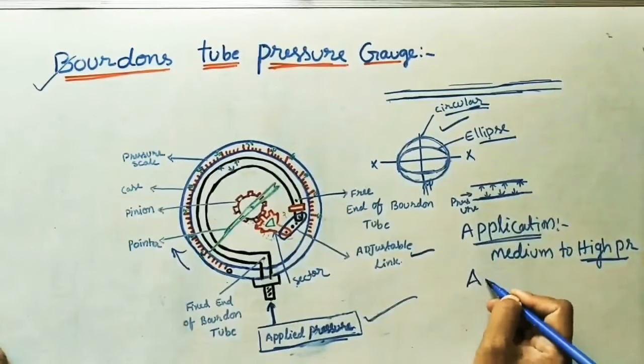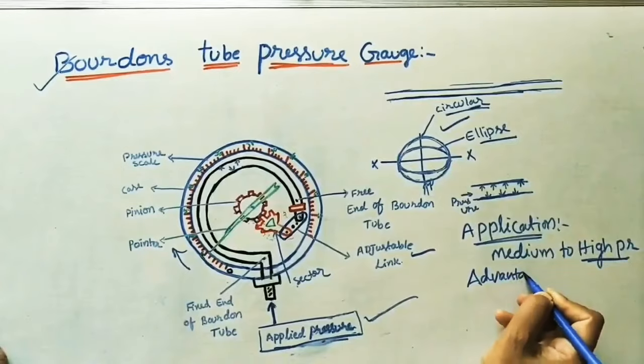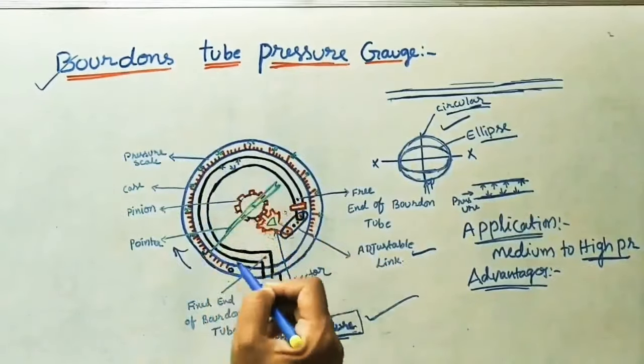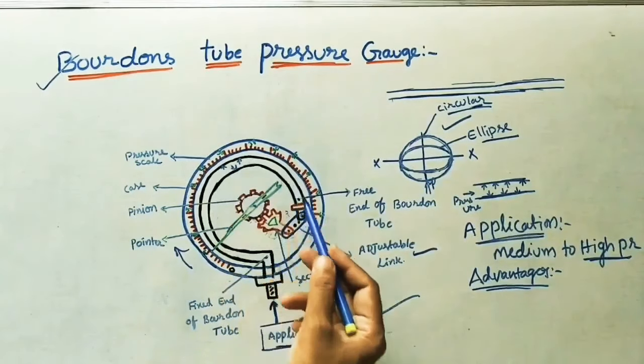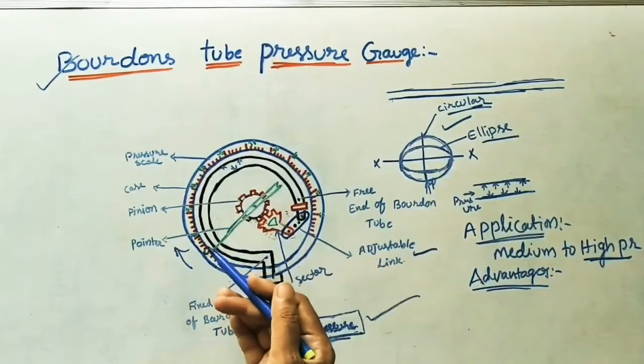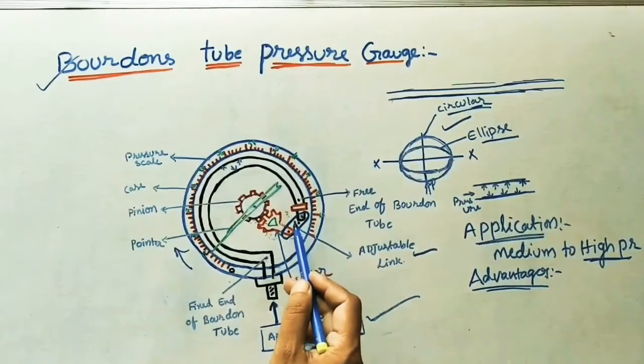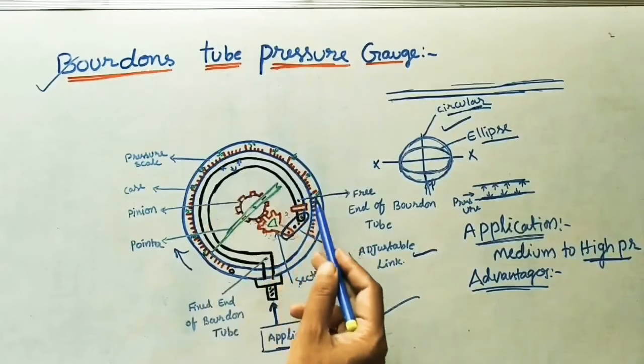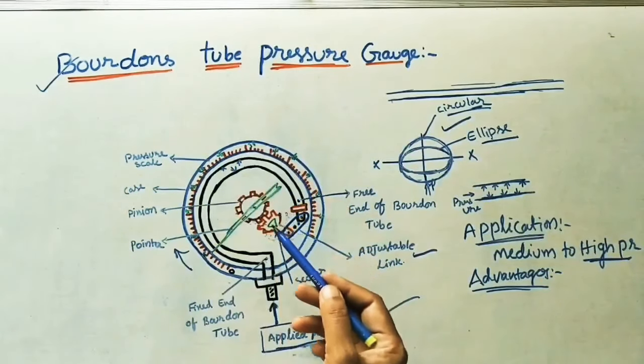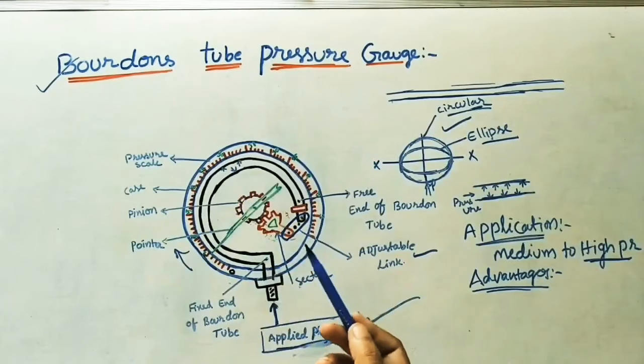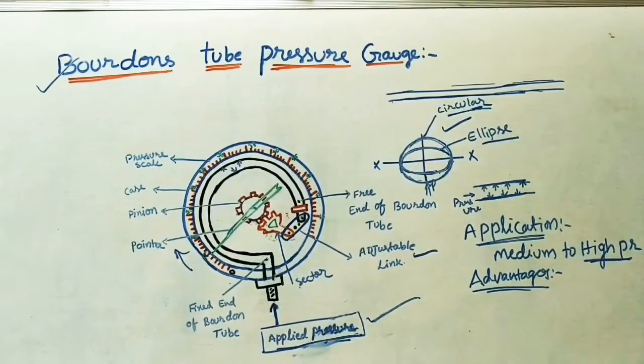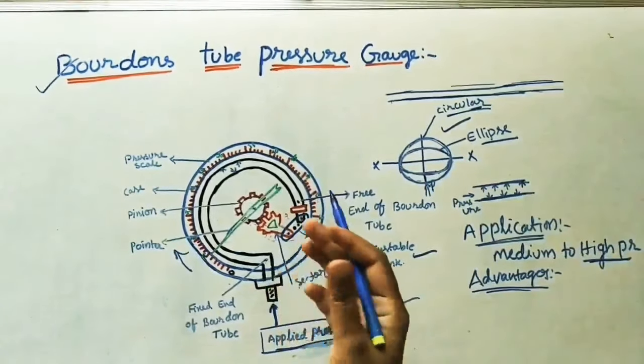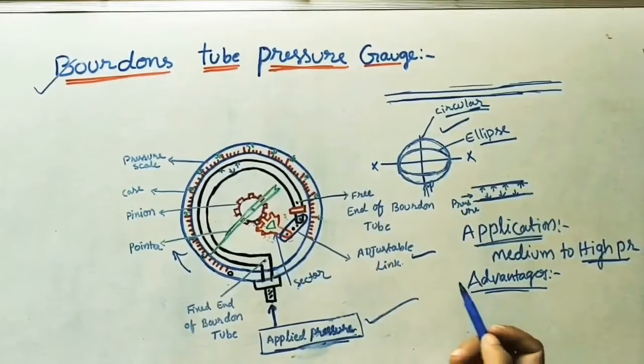The advantages of the Bourdon tube: it has a very simple construction — only one Bourdon tube is used — so the cost is less and the working process is very easy. It can be modified to give electrical outputs, allowing connection to a voltmeter or ammeter to show readings. Accuracy is more at high pressure, and some instruments may not work at high pressure whereas the Bourdon tube gives correct values.